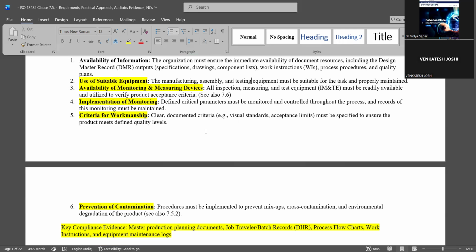Okay, some monitoring parameters will be provided by the machine itself. But the important thing is you need to check the systems that are giving you monitoring on the machine. Suppose the machine is providing you temperature. You should check whether the temperature it is providing is correct or not. So you need to calibrate it.